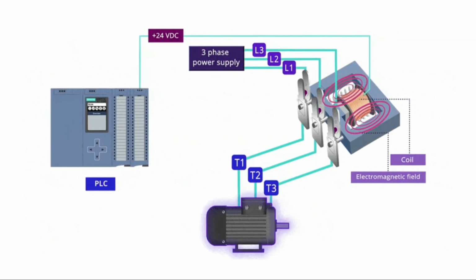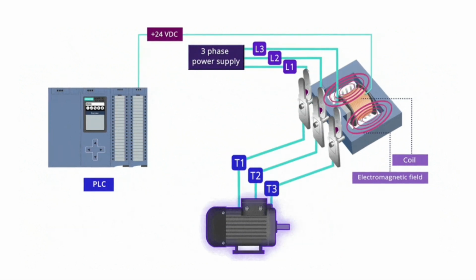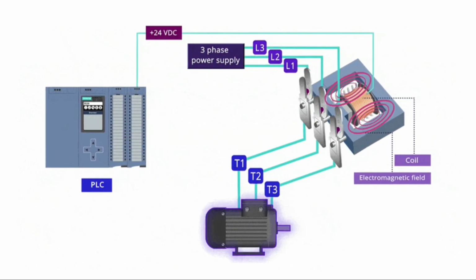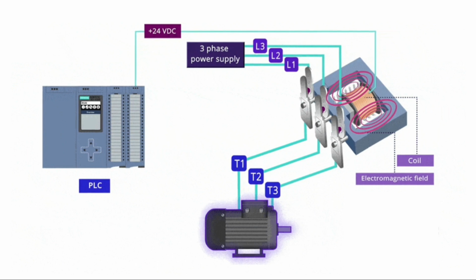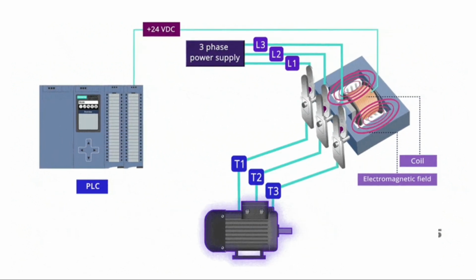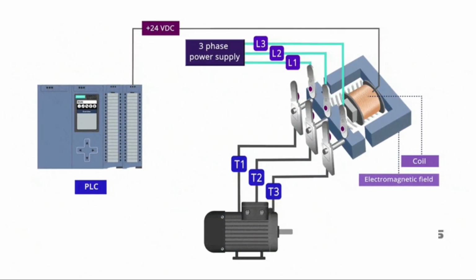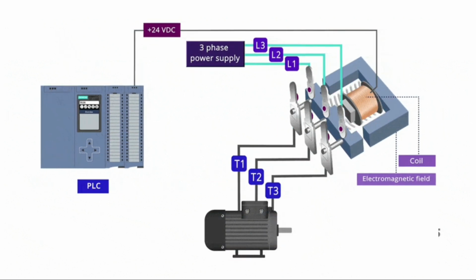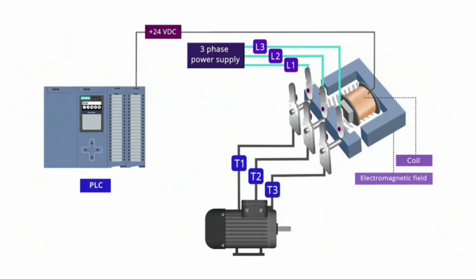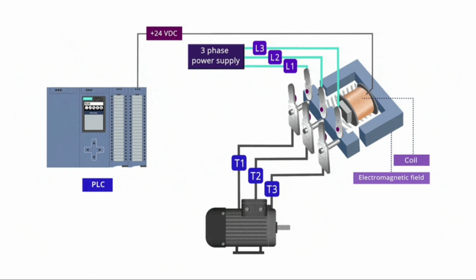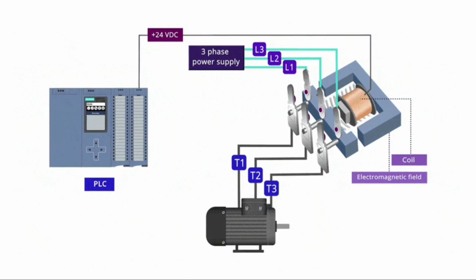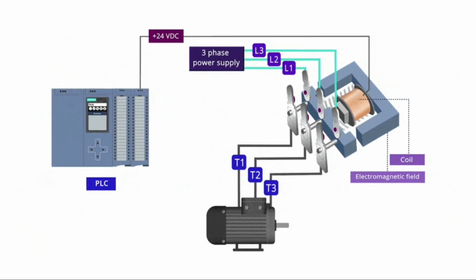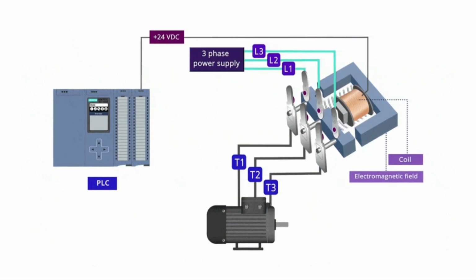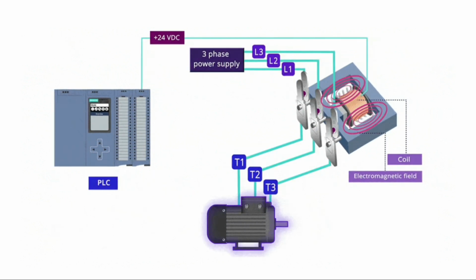What do we mean by indirectly, you ask? Well, all contactors have a low voltage coil. We connect the PLC output to this coil. This coil usually works with a 24-volt DC signal. Once the coil is energized, an electromagnetic field will be created. This electromagnetic field then causes the three contacts here to be closed, and that's how the three-phase power will reach the motor and can turn it on. Looks like magic, right?